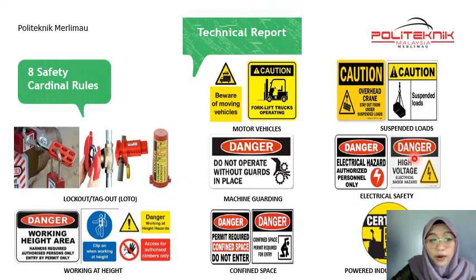Prior to servicing equipment, a check must be made with a proximity voltage sensor to ensure that the frames or control enclosures of equipment being serviced are not energized. No grounding check is required for factories that have conducted a grounding or GFCI inspection per SWI 004; otherwise, checks for energized surfaces must be completed.